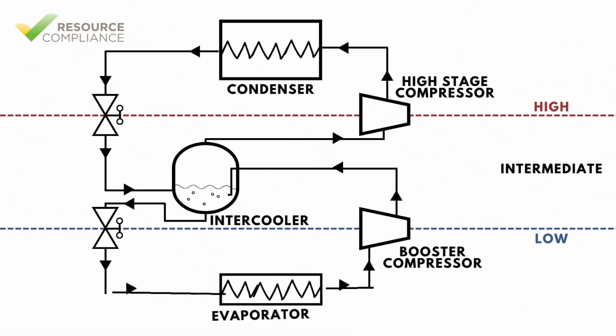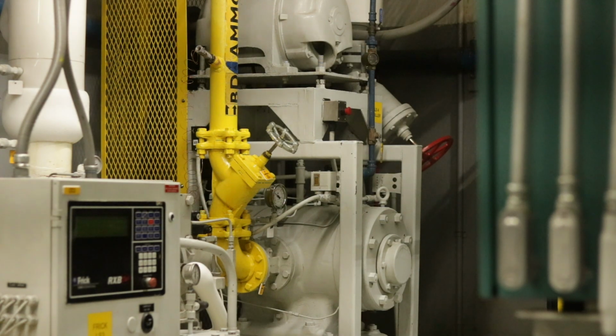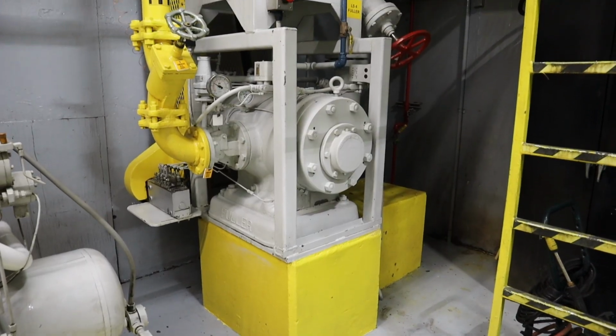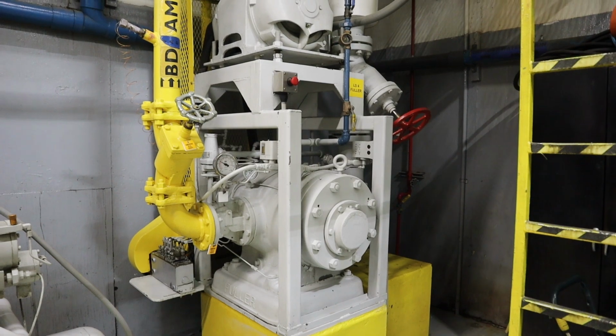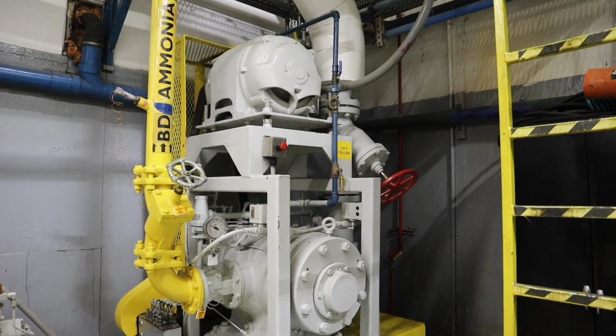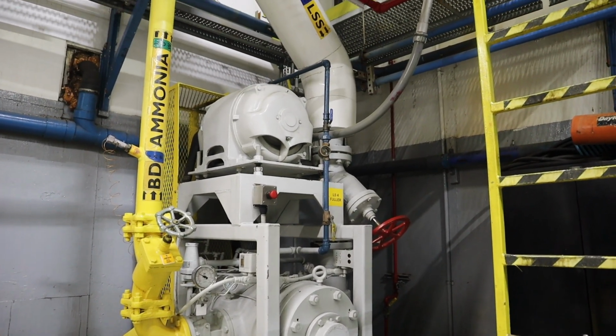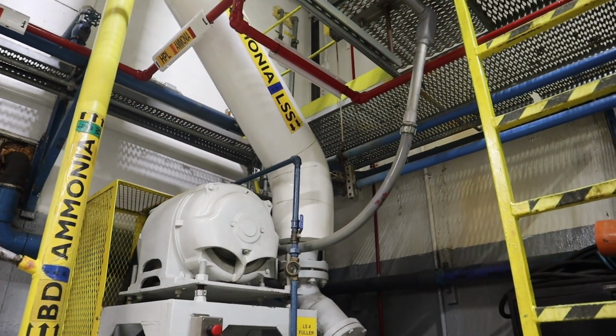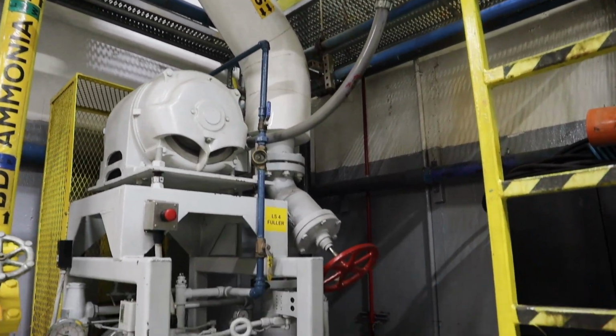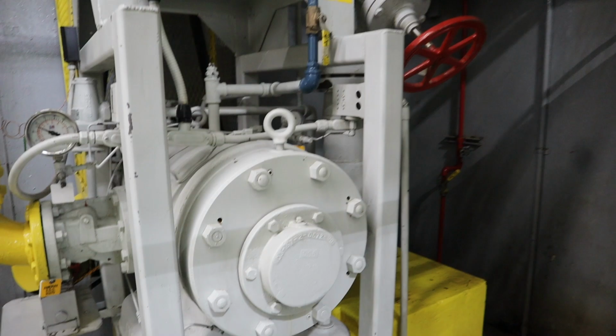For two-stage systems, the high-stage compressors must be started before the booster compressors. Rotary vane compressors are always used in booster applications, so this step would be necessary. Rotary vane compressors are often cooled by an oil jacket since water may freeze in a low-temperature application. The oil cooling pump must be started before the compressor. Another nuance for rotary vane compressors is that they are typically started with the suction isolation valve closed. Once the compressor is operating at full speed, the operator will slowly open the valve and monitor the suction pressure.